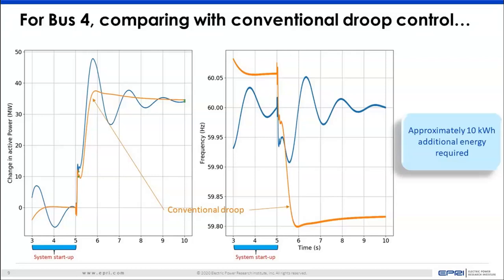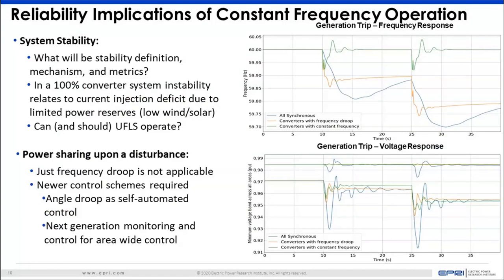Now, this has been applied from our end at EPRI to larger systems also, where we looked at a system which is very similar to the Texas system. It's not the real Texas system, but it's very similar in size and structure. For two subsequent losses of about 1 gigawatt of generation, the blue curve shows conventional frequency response with all synchronous machines. The orange curve shows inverter-based resources themselves providing Droop response. And the green curve shows our distributed slack bus approach, and just how fast and tight you can have frequency control with this incremental energy injection.